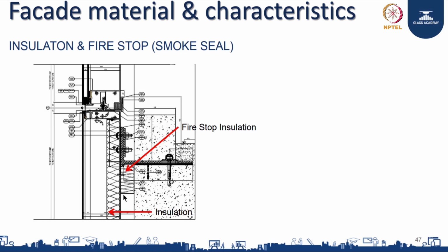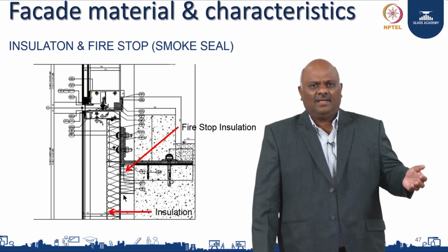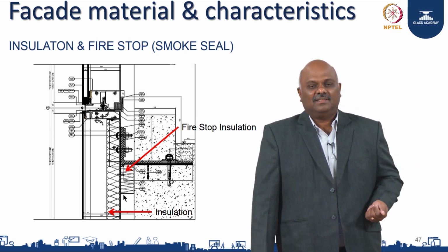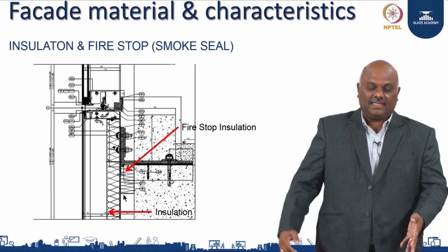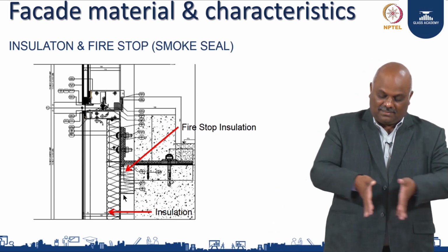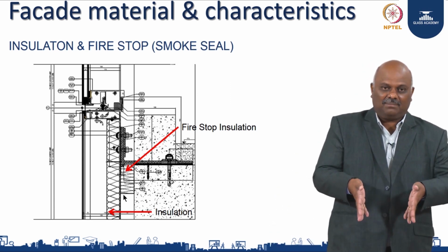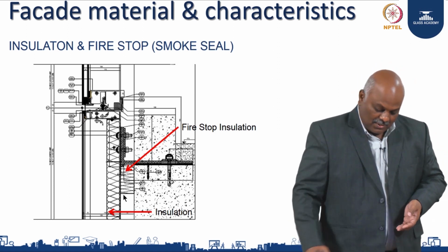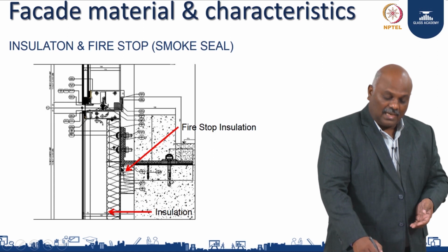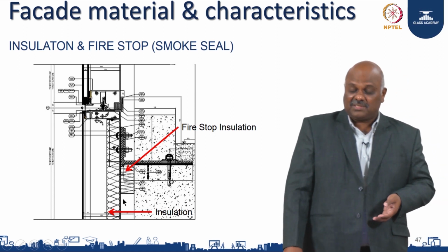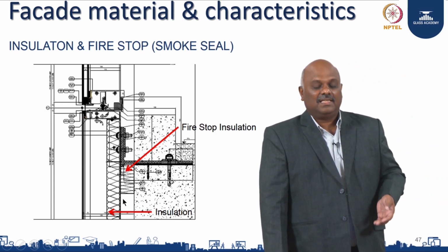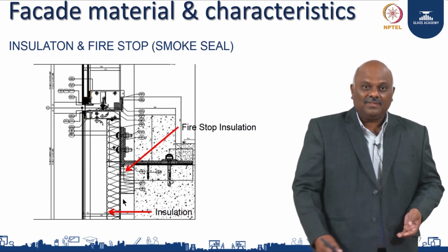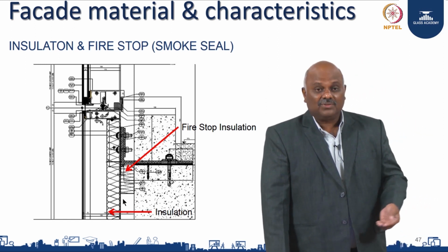The insulation takes care of this fire spread. It means you have a compacted system inside. It's compressed within the floor gap with a tray or some other system. So the smoke doesn't go from below. And the fire spread also, as it is a non-combustible material, it doesn't let the fire spread to the next floor. So it is both together.